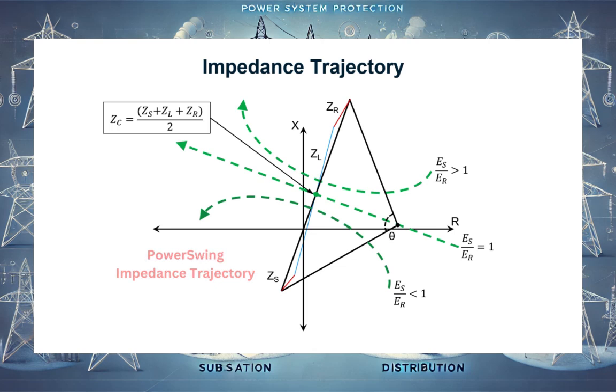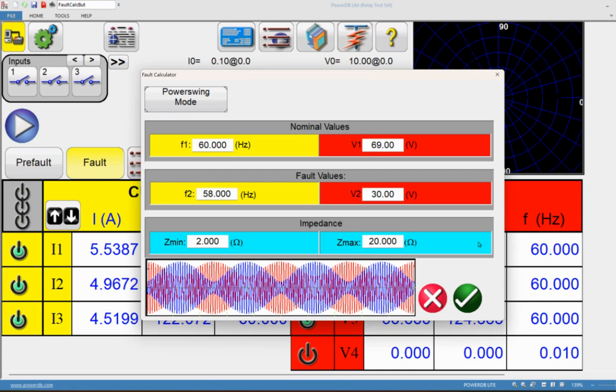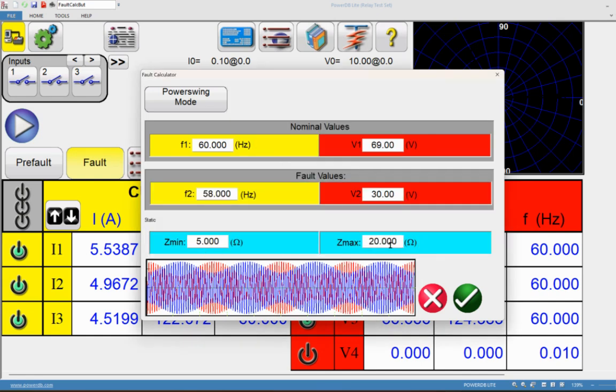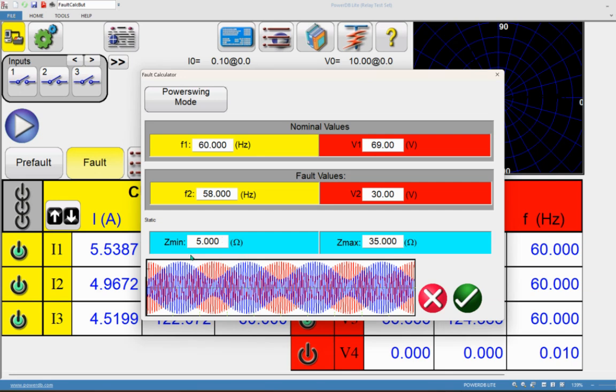Using the manual tool to test this scenario in the RTMS software: click on the fault calculator icon and select power swing mode. You have options for nominal values, fault values, and impedance settings. Assume you want to generate a power swing at a minimum impedance of 5 ohms and a maximum of 35 ohms — these define the boundary between which the swing is detected by the relay.